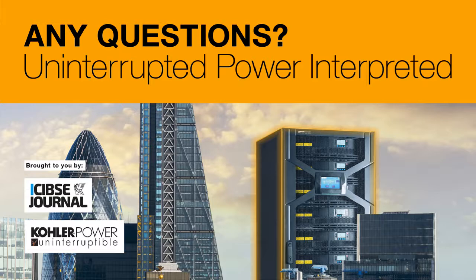Though, maintenance is extremely important, and to make sure we know that system's going to work, we should do it. My colleagues sort of looking. We've got a situation at the moment where we're having trouble in a hospital. We can't change the UPS without a shutdown because they haven't got a maintenance bypass. So, although it's not essential, it's a good option.